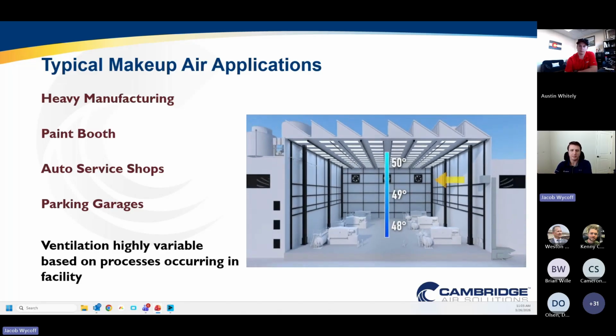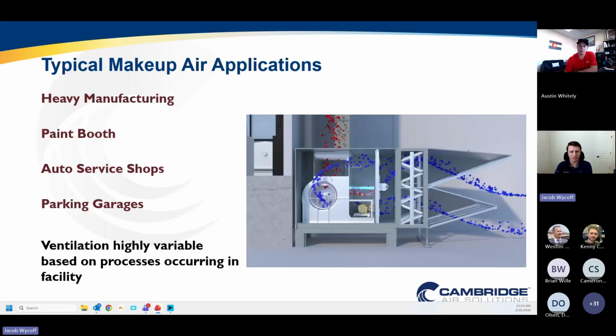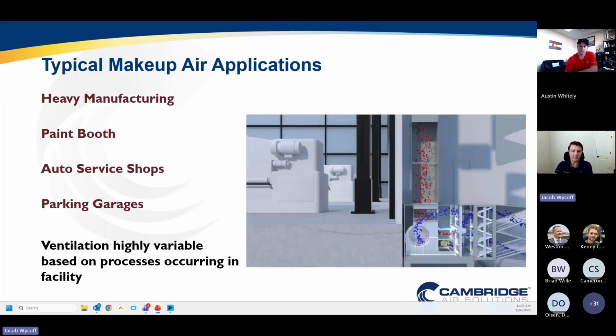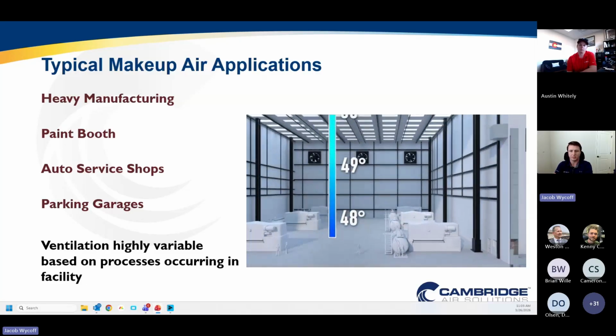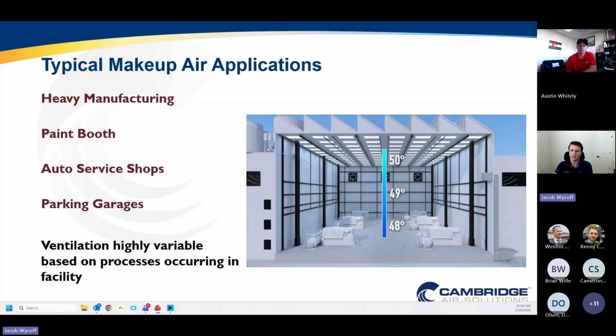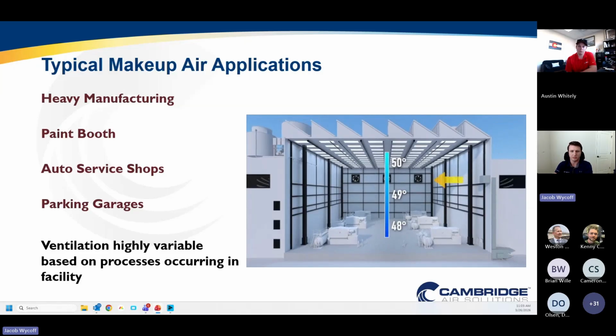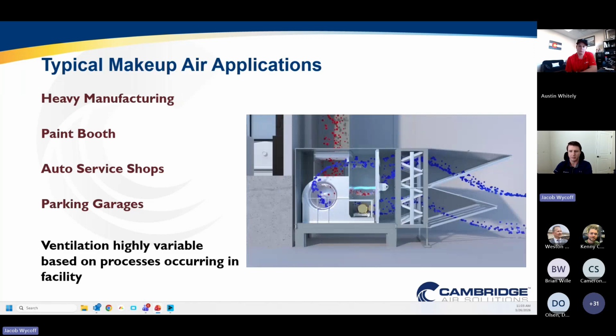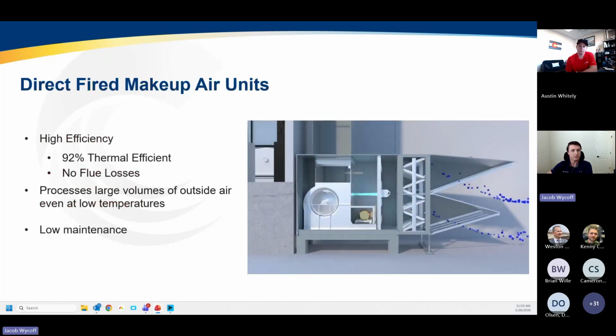air. And in any kind of application or climate zone where it's going to get below freezing, where it's going to get cold, you're going to have to heat that makeup air or at least temper that makeup air to avoid a whole host of issues like building pressurization issues, freezing the building, if you were to provide either unheated makeup air or not provide makeup air at all. So we at Cambridge Air Solutions, we believe that direct fired makeup air units are the best solution for these applications, really for a few key reasons.